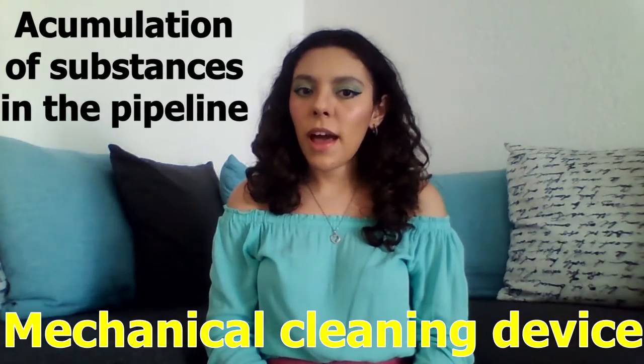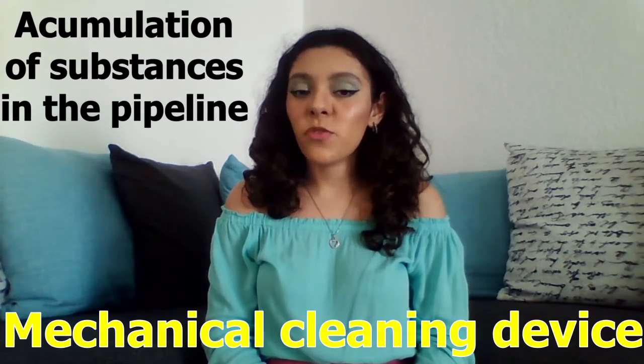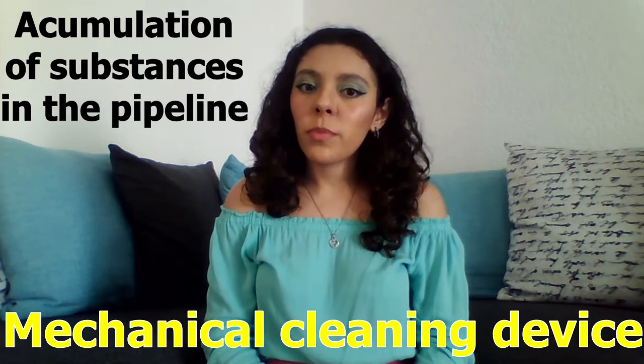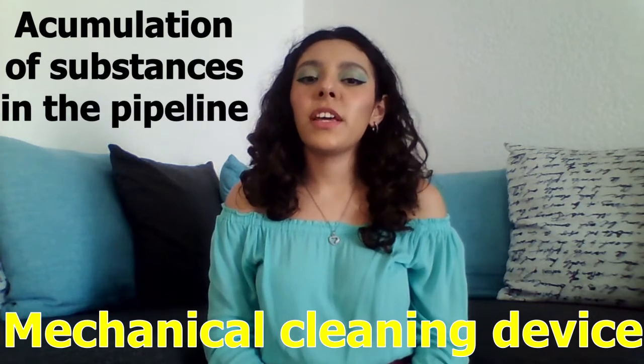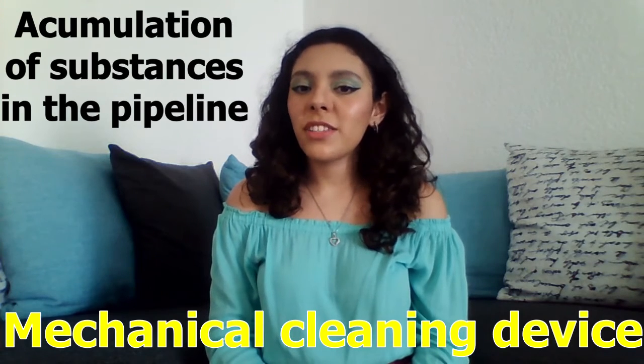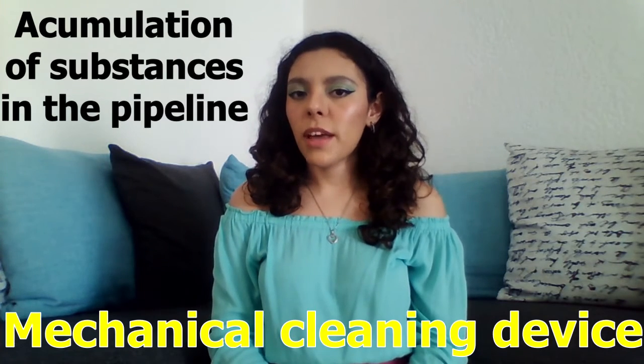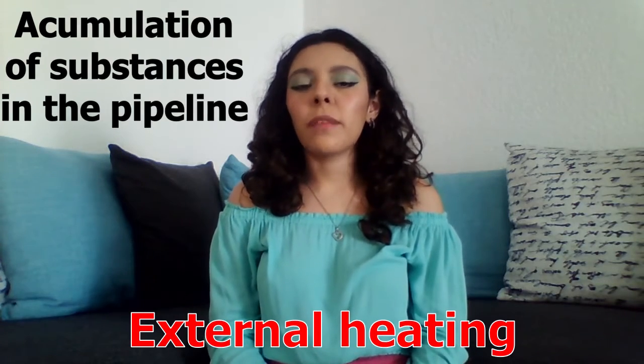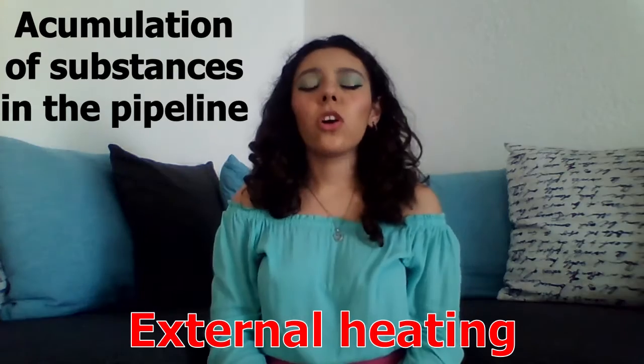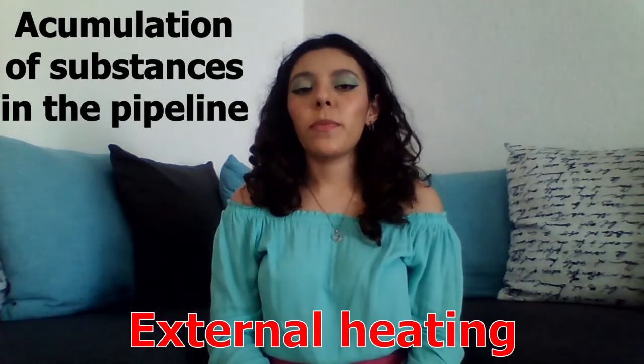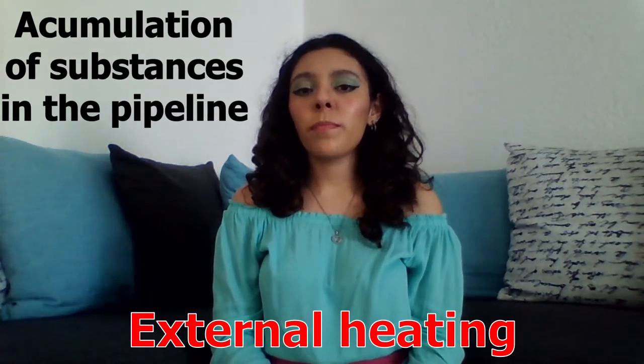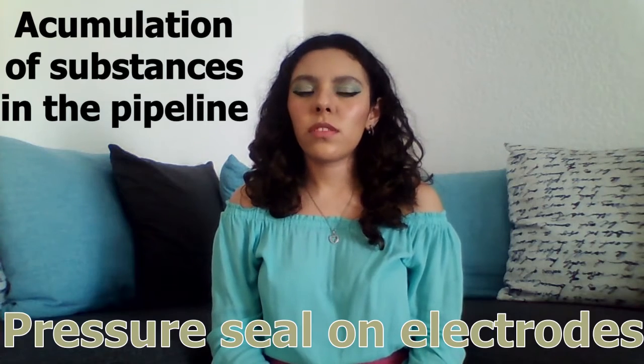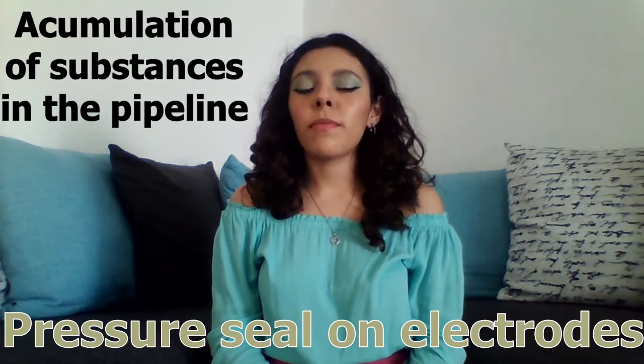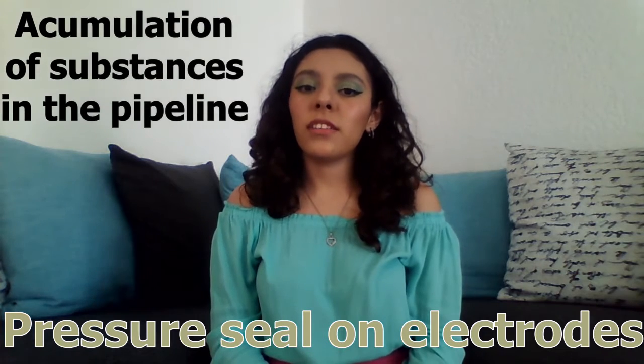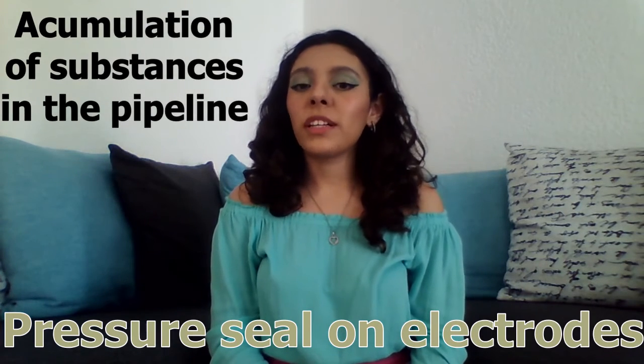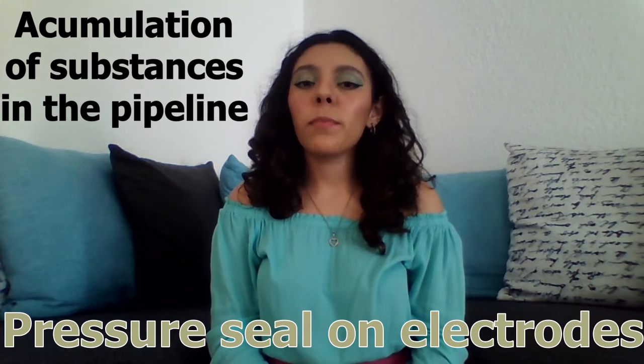The mechanical cleaning device consists of mechanical scrapers driven by a motor that continuously rub the surface of the electrodes. It must be taken into account that if the accumulated solids are very large, the device can be damaged. The external heating of the tubes can be carried out by resistant bands, controlled by a thermostat. Heating prevents grease or solids from depositing on the pipe walls. Pressure seal on electrodes. In other systems, the electrodes have a pressure seal and are contained in an easy-to-disassemble unit, which allows them to be cleaned or replaced without having to remove the measuring tube from the pipe.